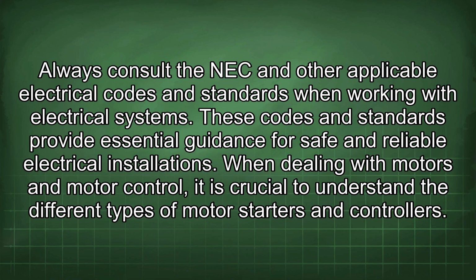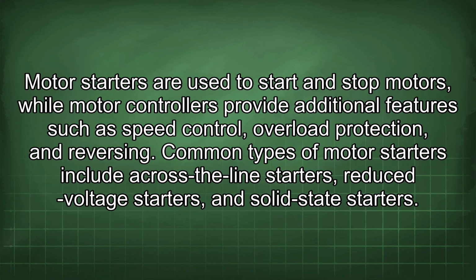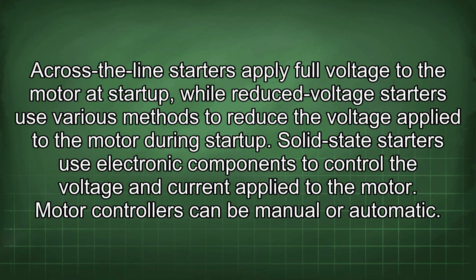When dealing with motors and motor control, it is crucial to understand the different types of motor starters and controllers. Motor starters are used to start and stop motors, while motor controllers provide additional features such as speed control, overload protection, and reversing. Common types of motor starters include across-the-line starters, reduced voltage starters, and solid-state starters. Across-the-line starters apply full voltage to the motor at startup, while reduced voltage starters use various methods to reduce the voltage applied to the motor during startup. Solid-state starters use electronic components to control the voltage and current applied to the motor.